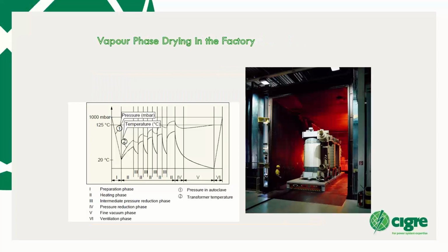First of all, there is a method to dry, and this is drying by vapor phase in the factory. It's a very effective method. But of course, you must bring the transformer to the factory. It takes a lot of time. It is maybe one of the most expensive methods. It delivers very good results, because then you can be sure that the solid insulation is really well dried.